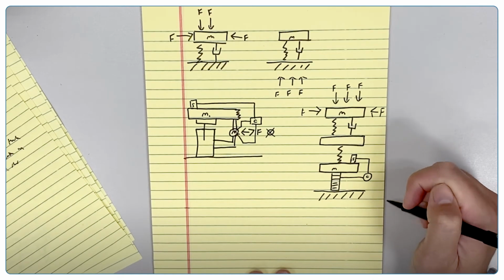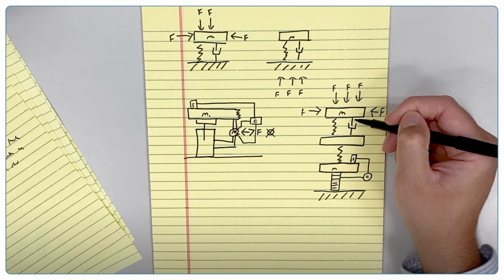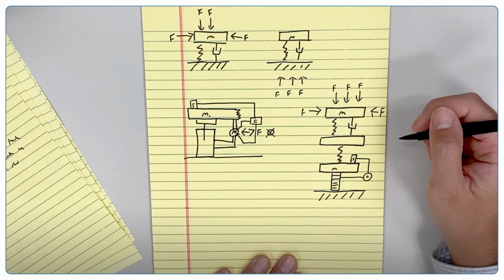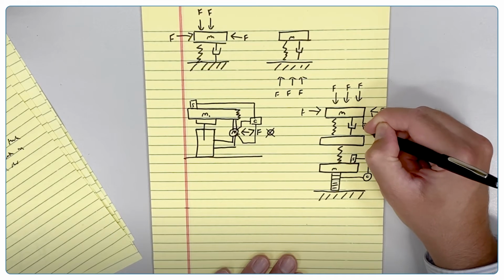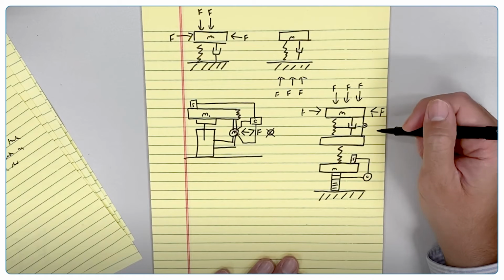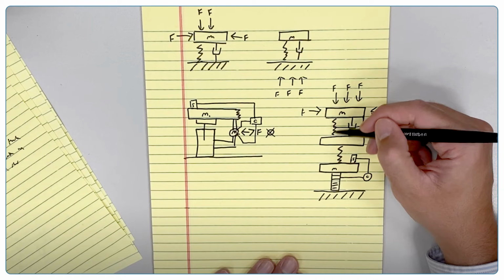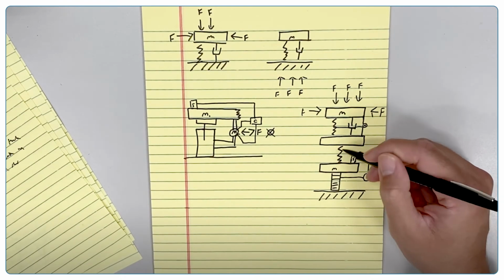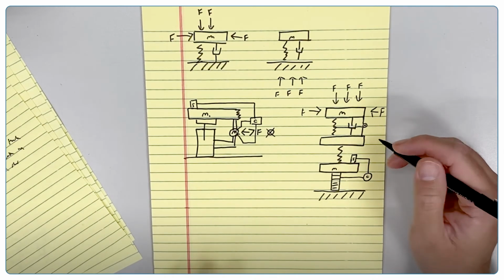Another advantage is the primary system can then be upgraded into its own motion cancellation system. So a linear motor and feedback and feed forward type technology can be added in parallel here to create a system that not only has excellent settling time and high frequency cancellation due to the soft spring, but also excellent low frequency cancellation and an independently operating floor vibration cancellation system.